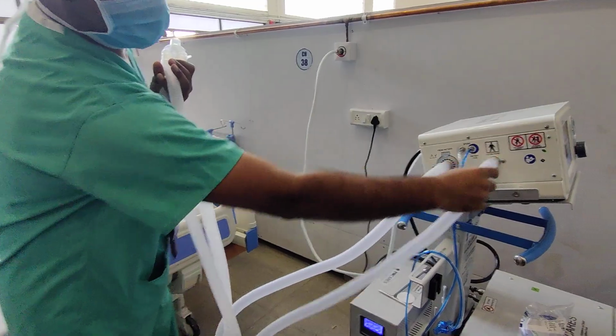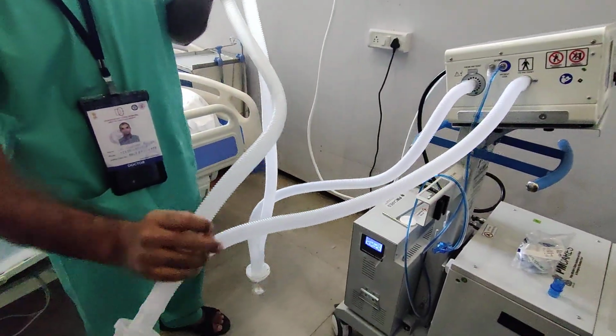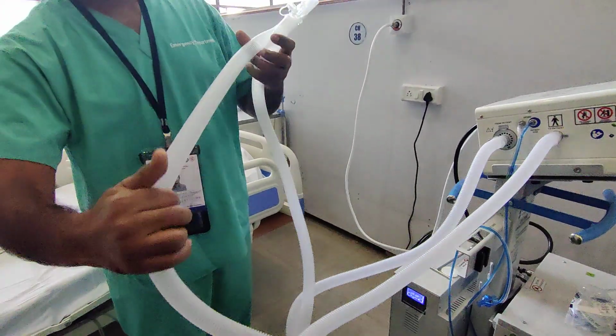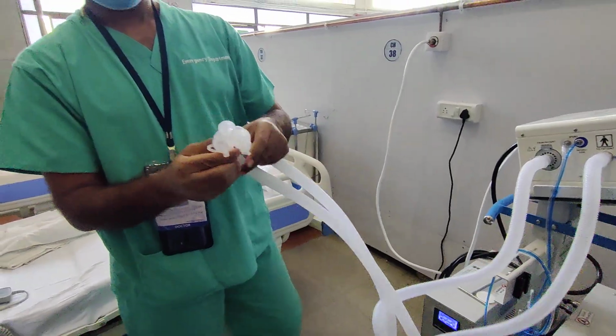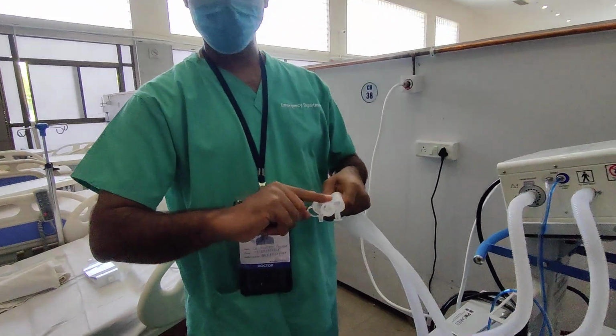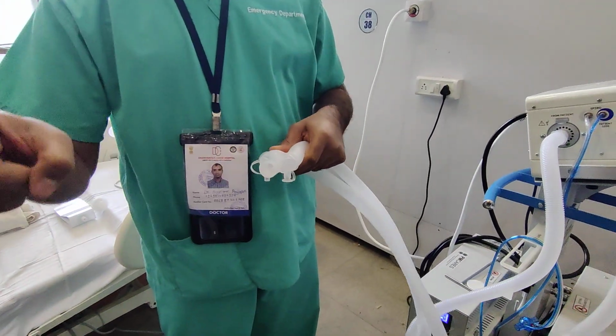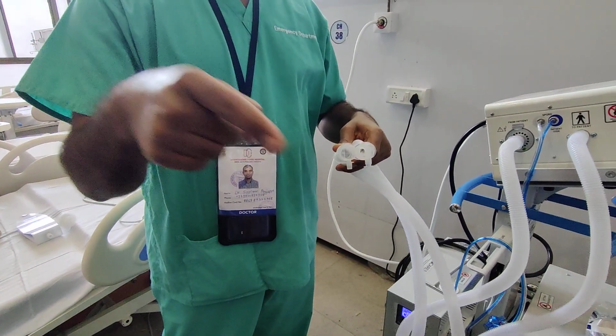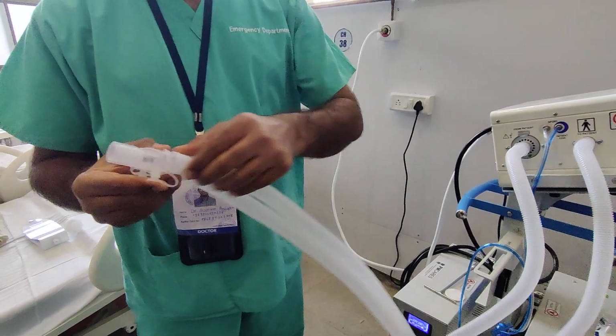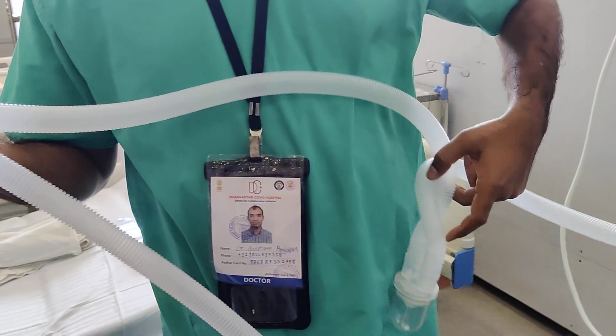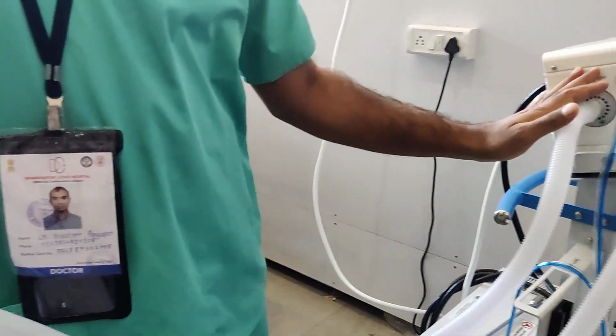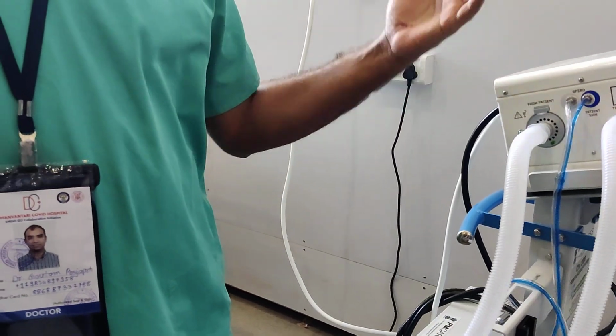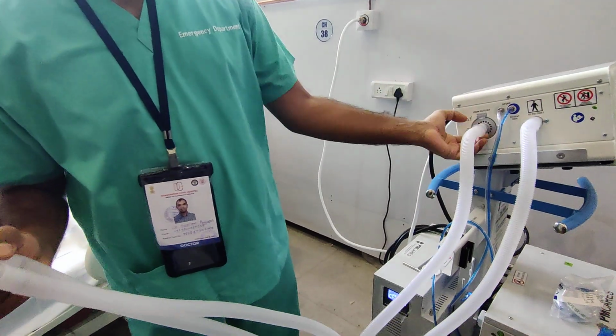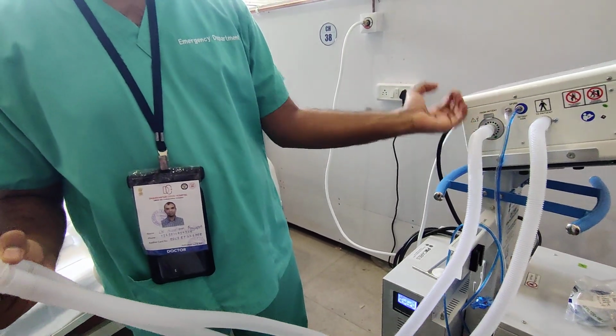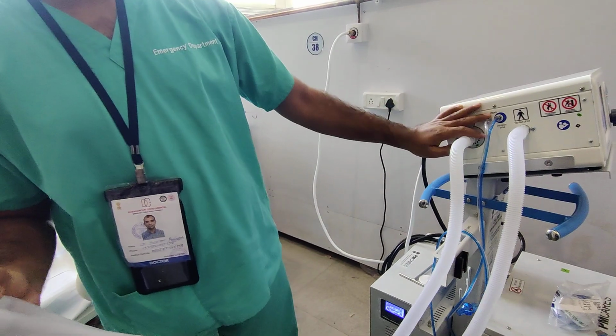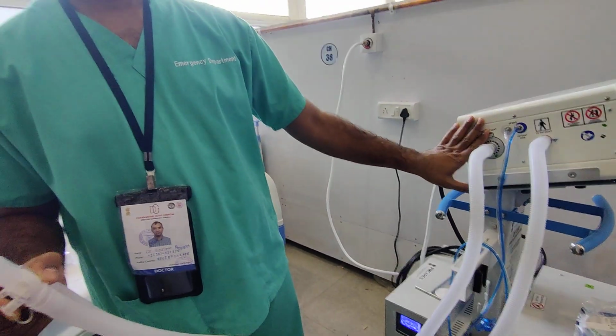This one is your inspiratory. So flow will come from this circuit, it will come here, and it will go to the patient from this Y connection. And when the patient exhales, the flow will come from patient here and it will go in this expiratory limb and into the ventilator, and the machine will exhale the air from this expiratory valve. So expiratory air will come out from the machine from here.